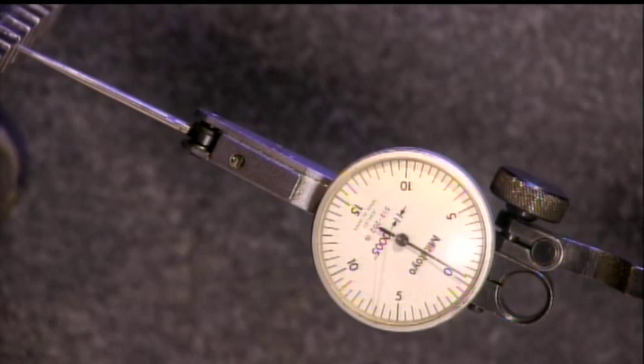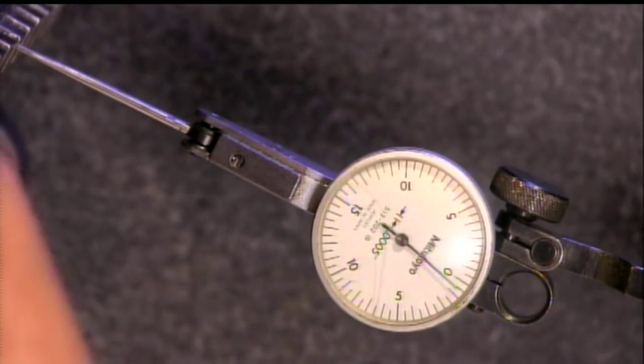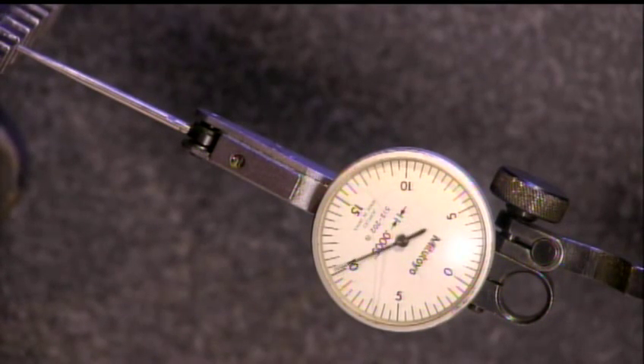So you move the gauge block stack 30 thousandths, and it only read 12. And that's with putting in a tip that's longer than it should be. That's too long for that dial indicator. It's just over 13 thousandths, so it's way off.